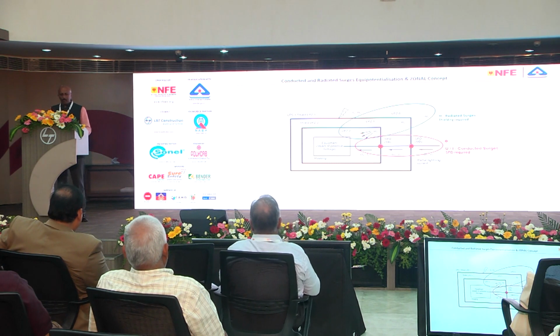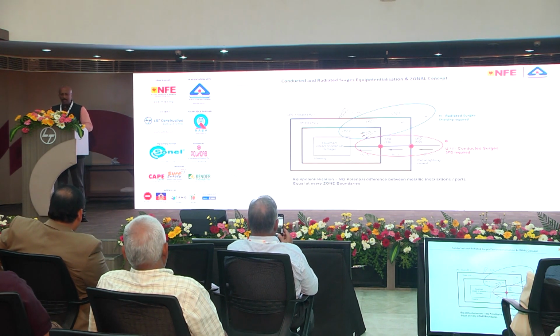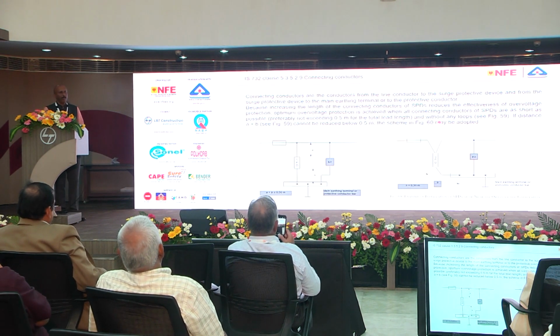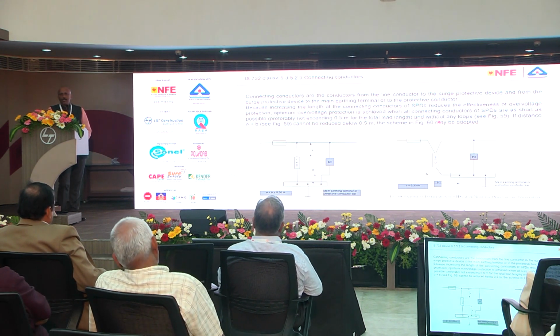Now let us go to the second part, the SPD. I have only 2 more slides, I will finish quickly. SPDs, as I told, depending upon the zonal concept, we are supposed to use. The first point you have to be very careful about while selecting an SPD is, once you connect an SPD, you have to use a very, very short wire for this connection.